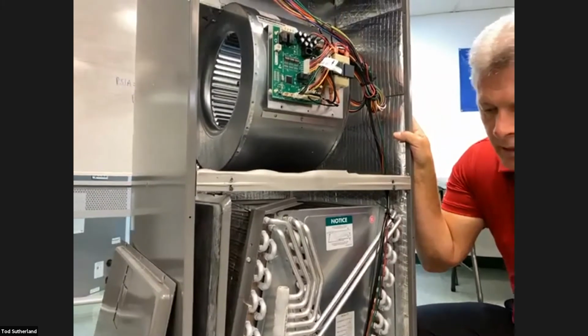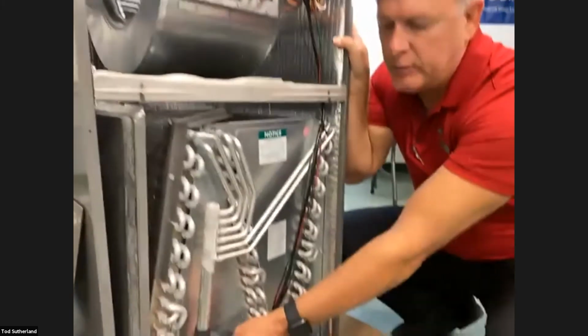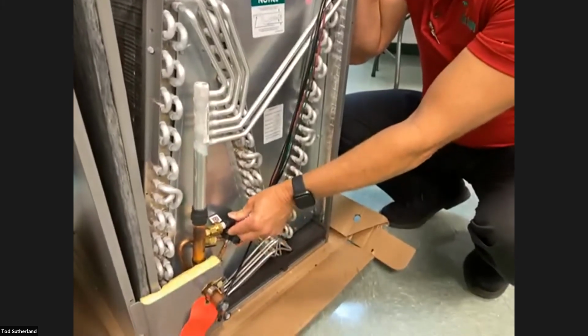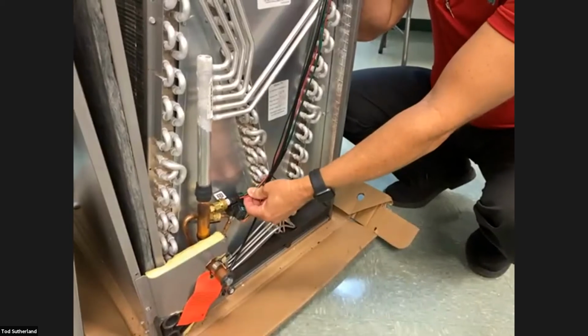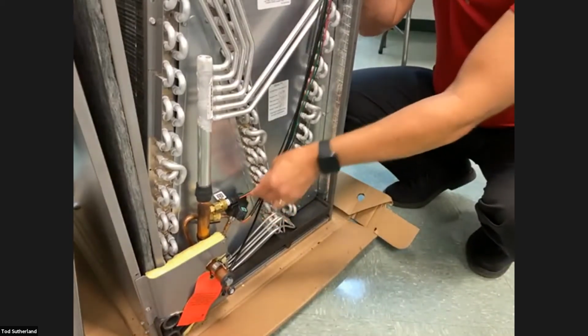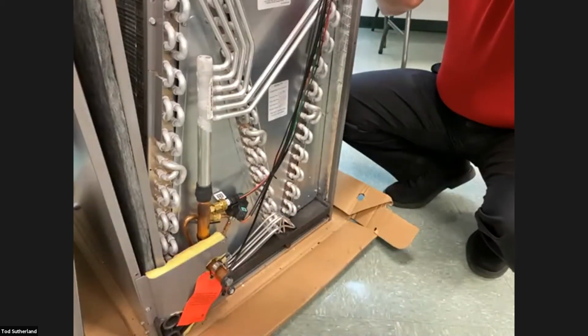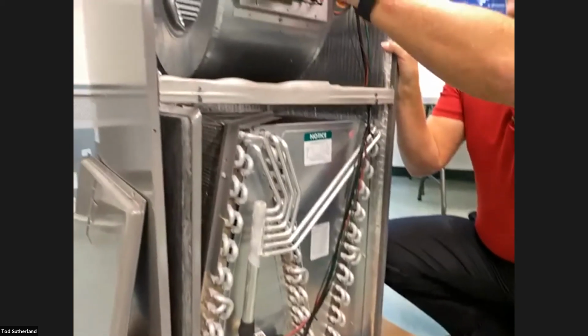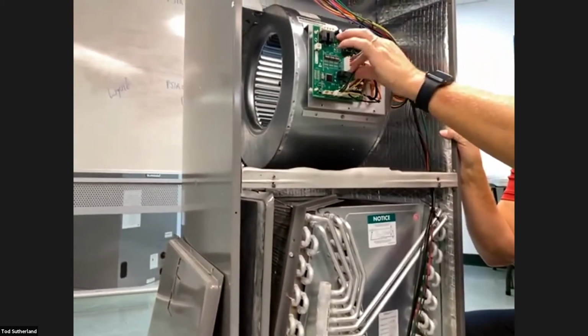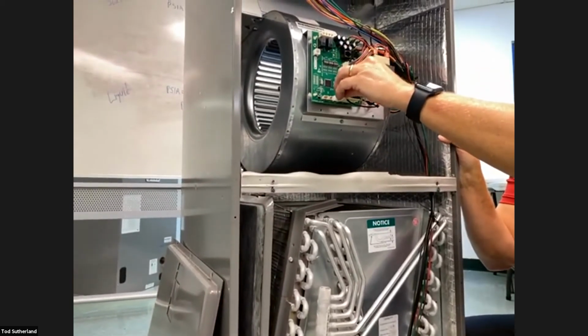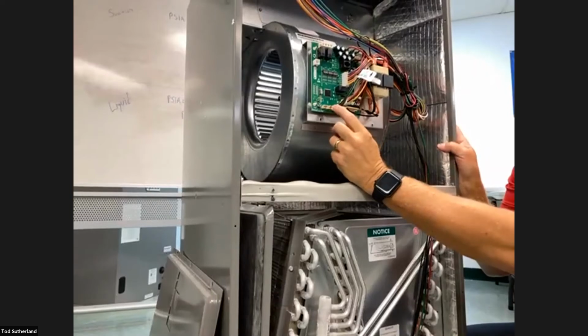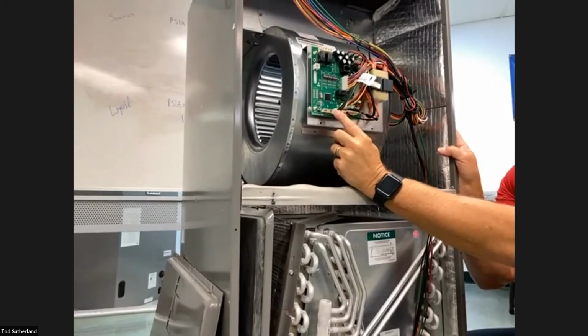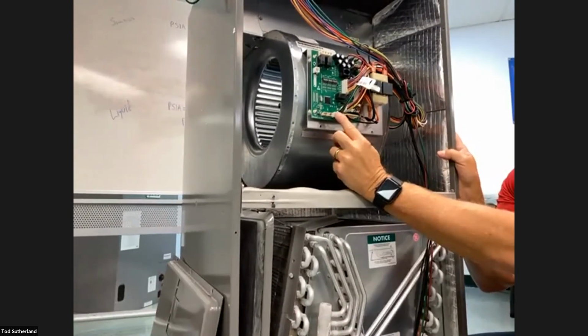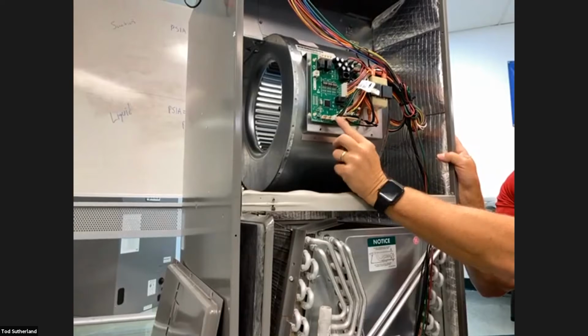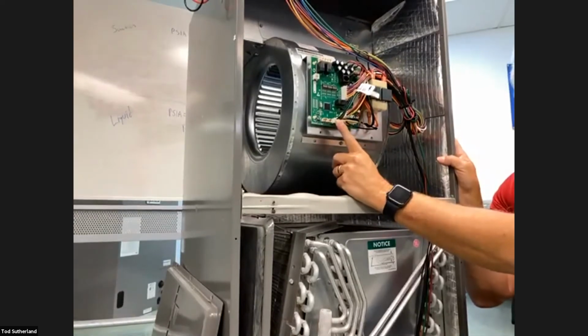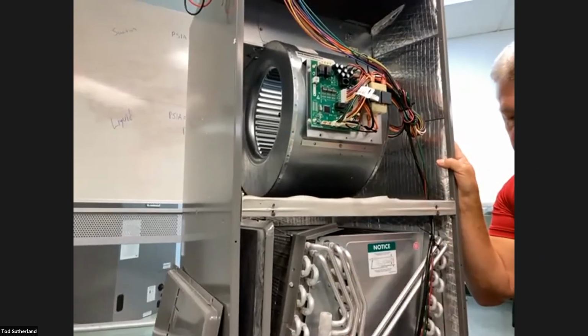Okay. This is the pressure transducer that we talked about. Your suction pressure transducer, you've got your red, green, and black wires here. They come up to here onto the board. Now to test these, you're going to want to make sure you've got power to the board. Once you have power to the board, you're going to take your probes and measure the output from the red to the black, and you should be getting 5 volts DC from the board to the pressure transducer.